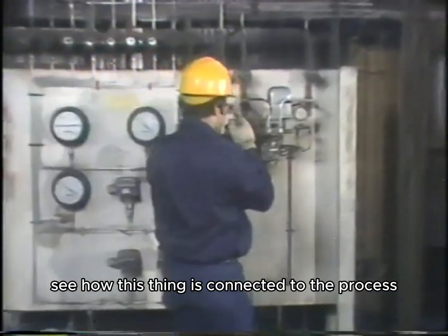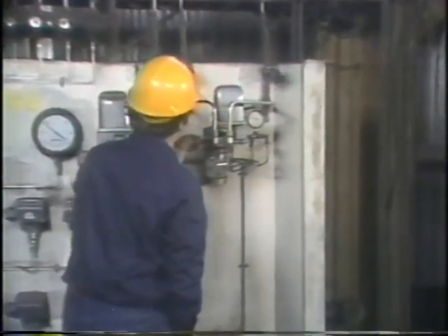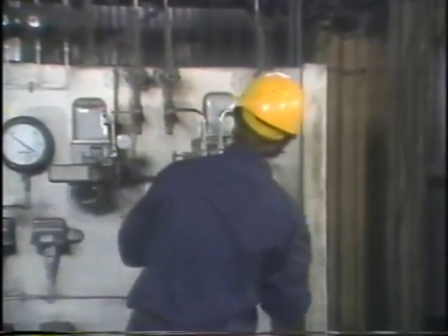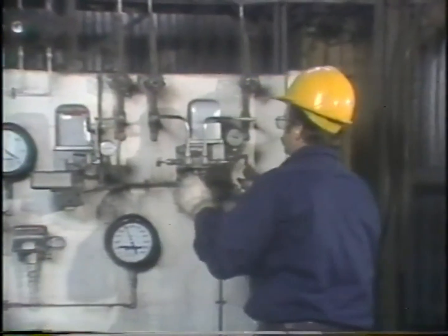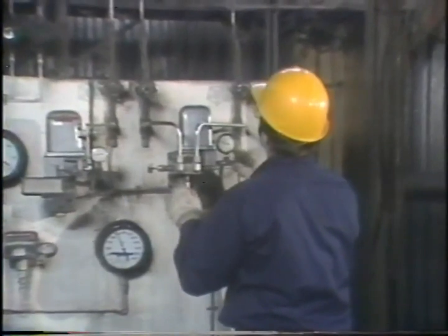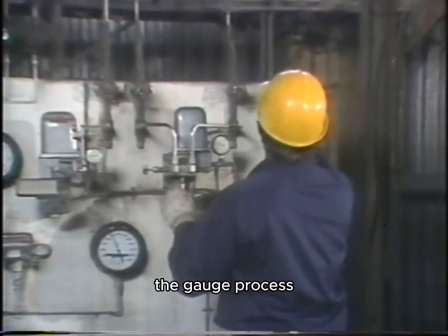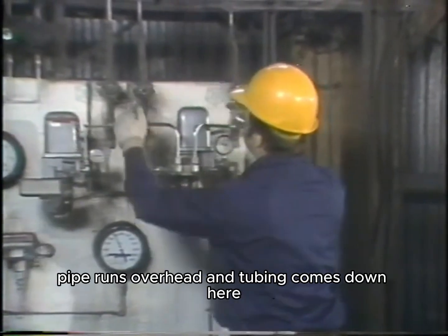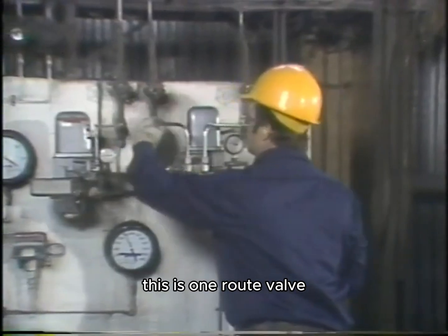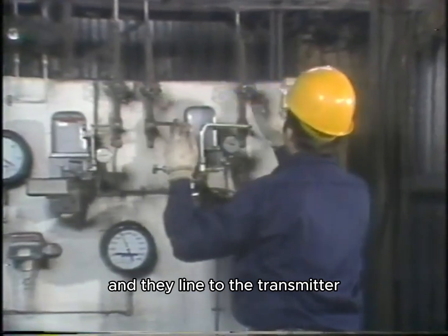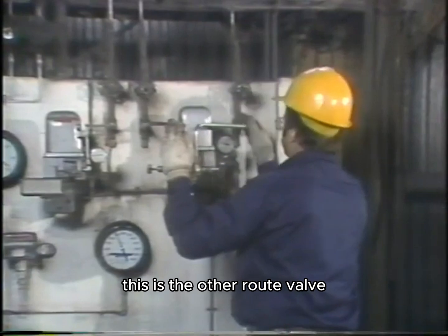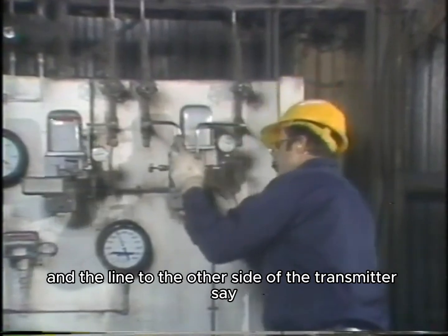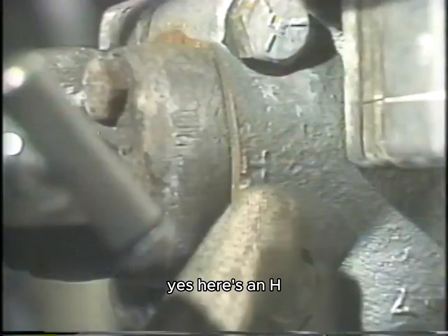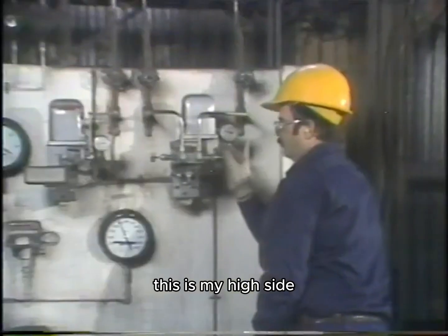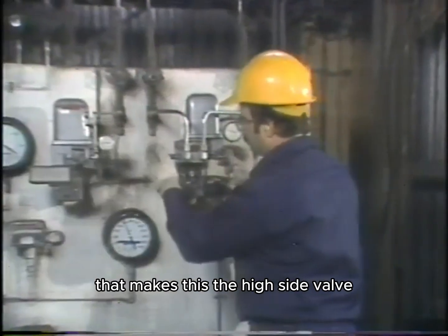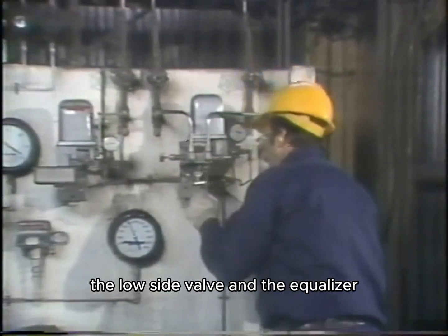Let's see how this thing's connected to the process. Gauge. Process pipe runs overhead, and tubing comes down here. This is one root valve, and the line to the transmitter. This is the other root valve, and the line to the other side of the transmitter. See, yes, here's an H. This is my high side, so that makes this the high side valve, the low side valve, and the equalizer.